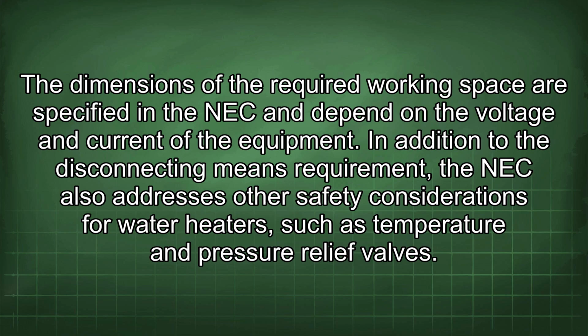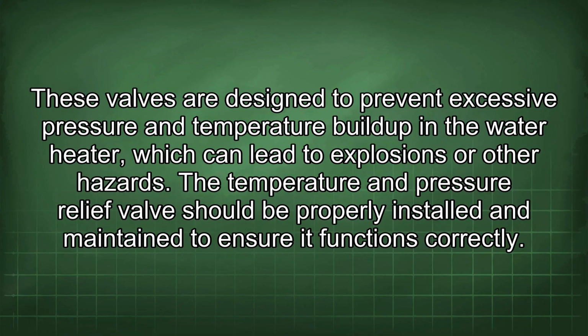In addition to the disconnecting means requirement, the NEC also addresses other safety considerations for water heaters, such as temperature and pressure relief valves. These valves are designed to prevent excessive pressure and temperature buildup in the water heater, which can lead to explosions or other hazards. The temperature and pressure relief valve should be properly installed and maintained to ensure it functions correctly.